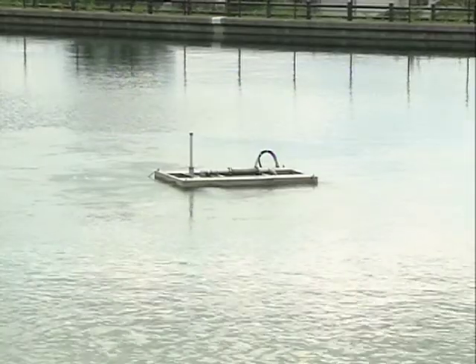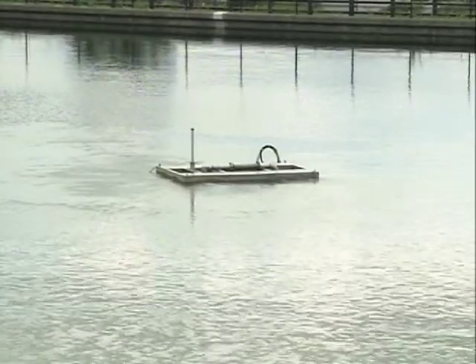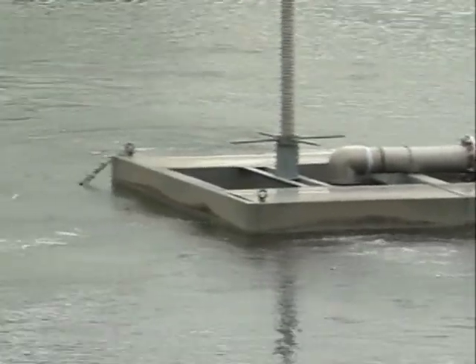The microbubble generator draws up water from the bottom of the reservoir, adds microbubbles to it, then pumps it out in 6 directions. This process infuses the water in the whole reservoir with a sufficient amount of air and causes the water to circulate, thereby preventing the growth of blue-green algae.